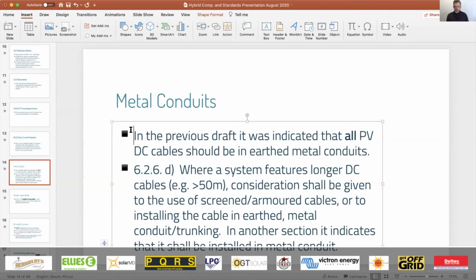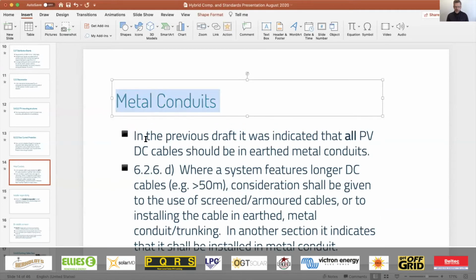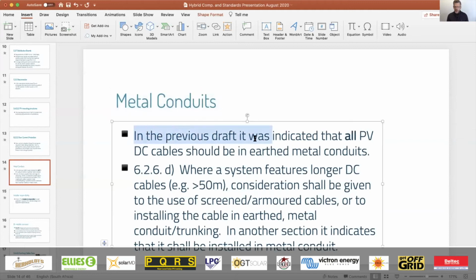So there we go. Metal conduits. A lot of questions about metal conduits. In the previous draft, it was indicated that all DC cables should be earthed in metal conduits, and all DC cables should in fact be housed in metal conduit. But that has changed in the new standard, where it says where a system features longer DC cables, in other words, longer than 50 meters, consideration shall be given to the use of screened or armored cables or to installing the cable in earthed metal conduit or trunking.